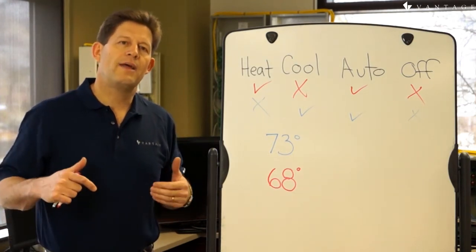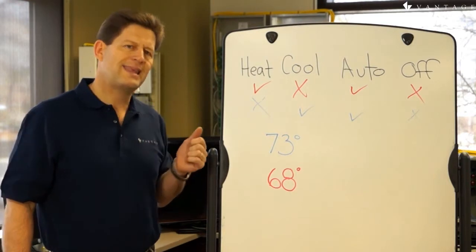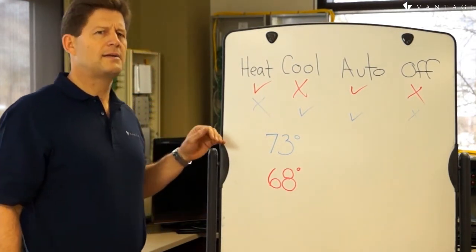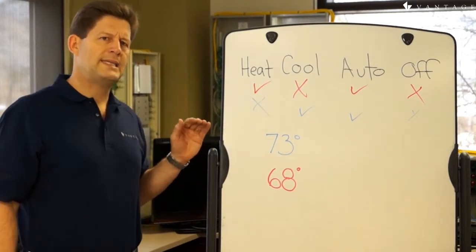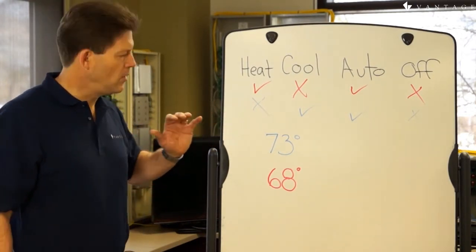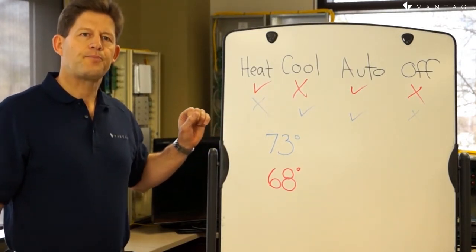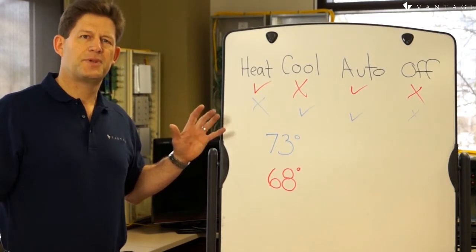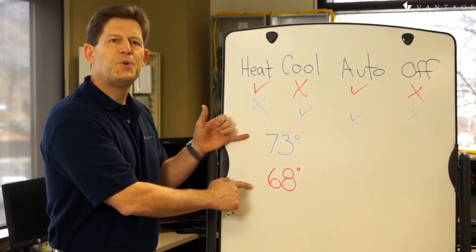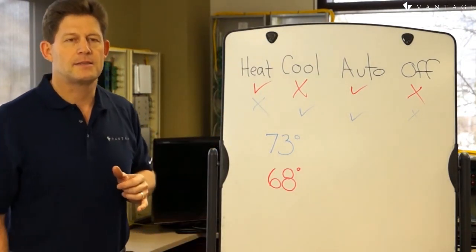Now that we've reviewed the operation modes and set points, let's talk about how you might think of set points. You might in some context think of them as a target temperature at which you want to maintain the space. This is particularly true when in only one system mode, like heat or cool. But in other contexts, particularly when the space is unoccupied, we think of the two set points as defining the acceptable temperature band limits.